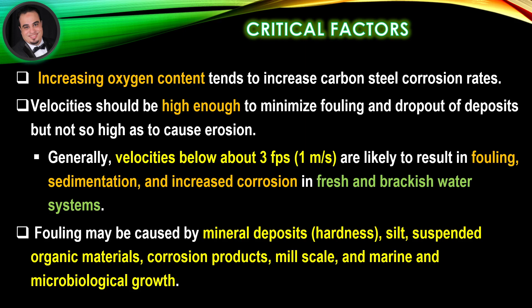Velocities should be high enough to minimize fouling and drop-out of deposits, but not so high as to cause erosion. Generally, velocities below about 3 feet per second are likely to result in fouling, sedimentation, and increased corrosion in fresh and brackish water systems.